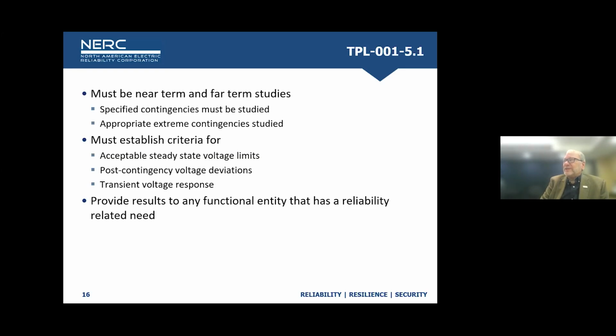You also, under N-1, cannot have any transmission overloads or any uncontrolled islanding for that area. For extreme contingencies, you might have a corrective action plan that requires the operator to take action, but you wouldn't necessarily have to construct for any of the extreme contingencies that you study there. And again, you have to provide the results to any functional entity, any entity that has a reliability related need to have the information from those studies.